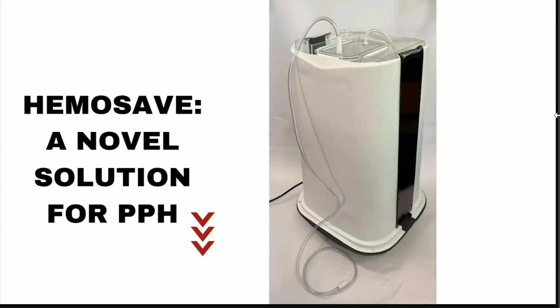So here's our solution, the HemoSave device. And the way this works in the OR is basically in two main pathways. The first option healthcare providers have is to aspirate all the fluids in the surgical area that they can into our suction container. When inside, two measurements are going to be taken, a colorimetric measurement and a gravimetric measurement. And so what we're getting from those is the volume of fluid in the container, as well as the percentage of blood that's mixed with the amniotic fluid. When you multiply those together, you get total volume of blood lost.